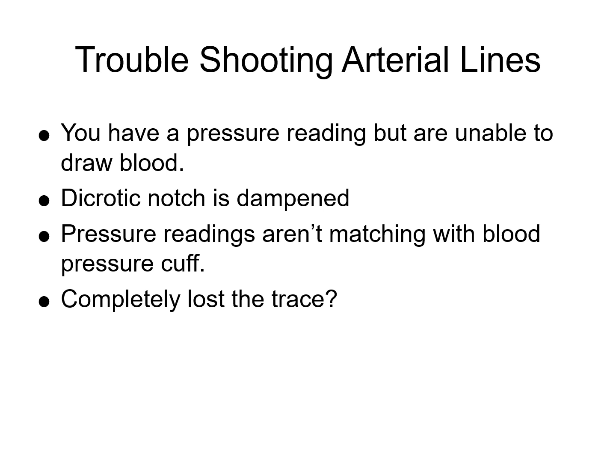Look to see if the pressure transducer is leaking, which would give you false low readings. If the pressure transducer is too high in position, I'll go over where it's supposed to be, then you're going to have a false low reading, and if it's positioned too low, you're going to have a false high reading. The pressure transducer should be placed at the level of the right atrium.